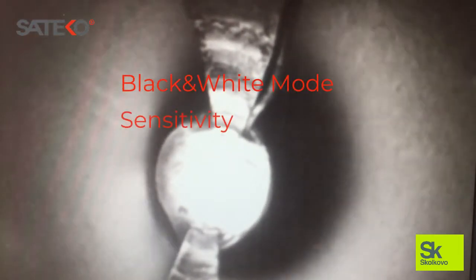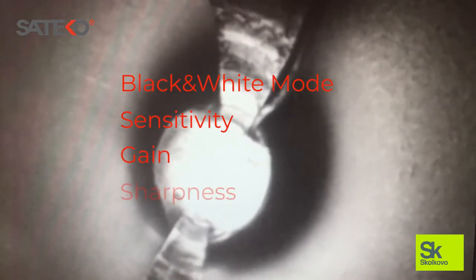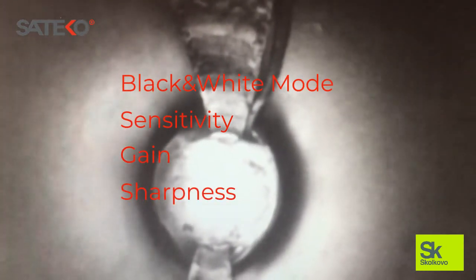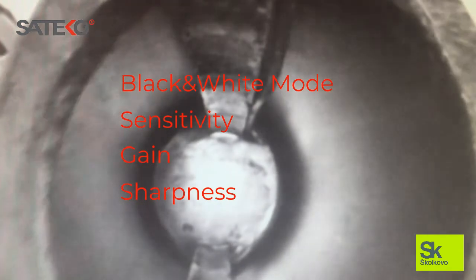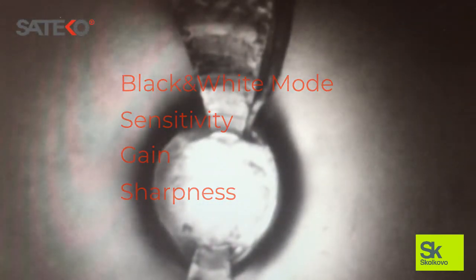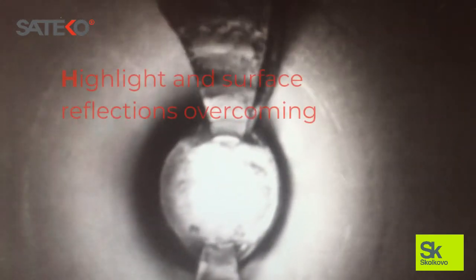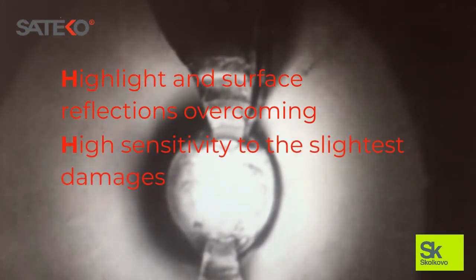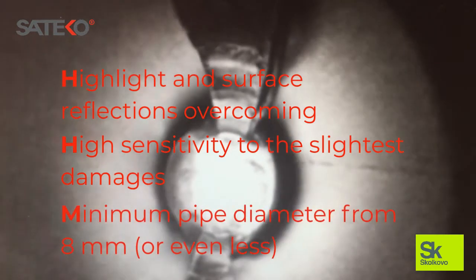To improve the accuracy of the image, we did a little work with the camera settings. We switched it to black and white mode to increase the sensitivity level of the sensor and slightly changed the internal settings of the processor, such as the signal gain level and sharpness. So, the advantages of the new SATEKO solution are overcoming highlight and surface reflections, high sensitivity to the slightest damages, and a minimum pipe diameter from 8 mm.